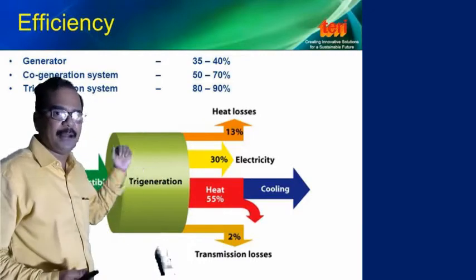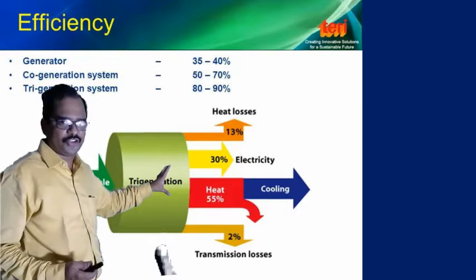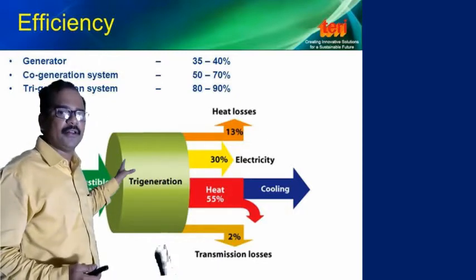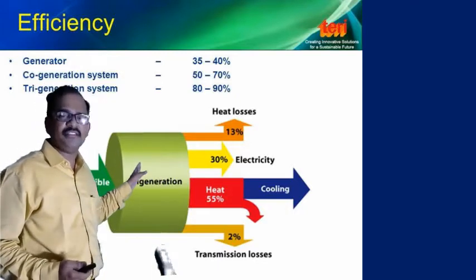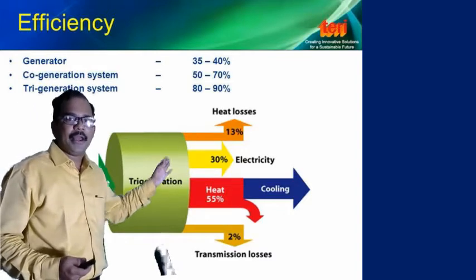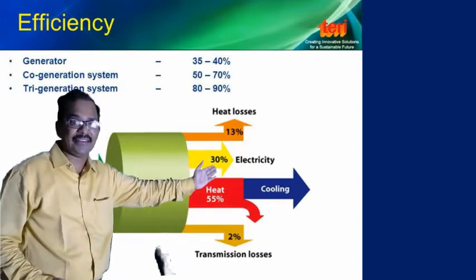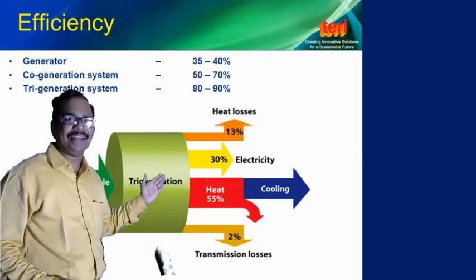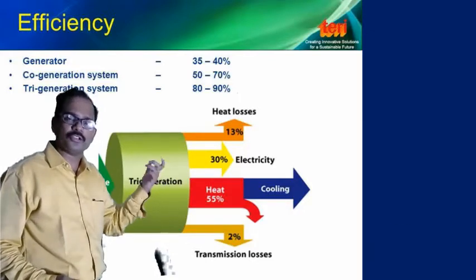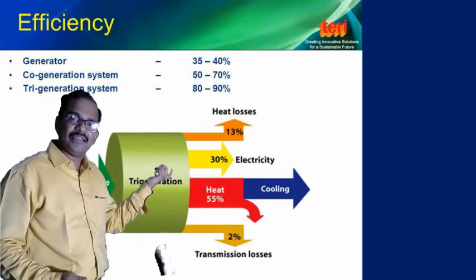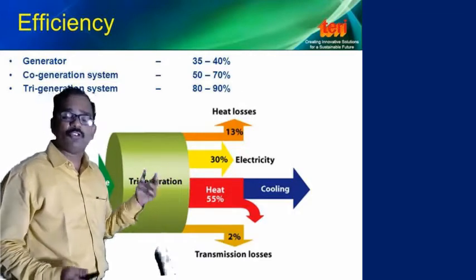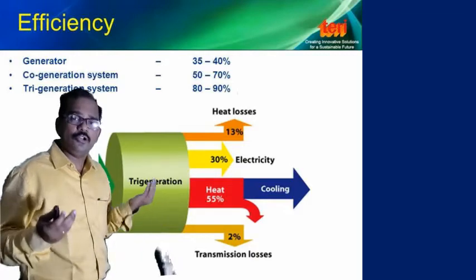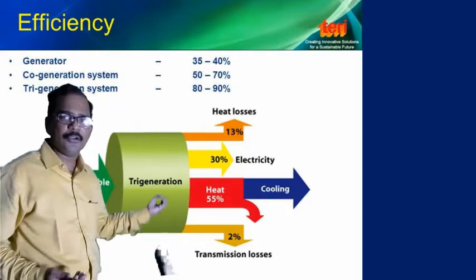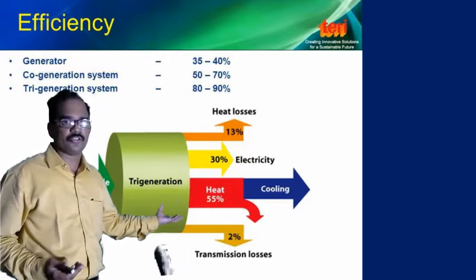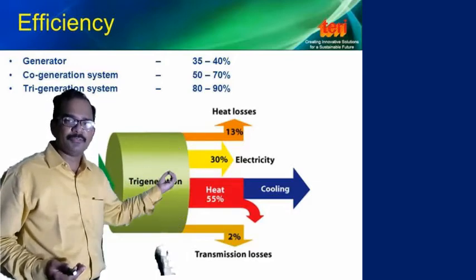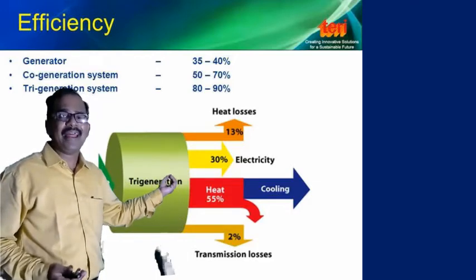You can see a typical example here. There is a trigeneration system. I have given 100% combustible fuel. That is, a fuel is combusted, and then I am getting 30% electricity and 55% as heat and cooling. Both are called thermal energy. It may be either heat or cooling. And what is the leftover 15%? That is losses. 13% heat losses and 2% transmission losses. So overall 30% electricity plus 55% heat and cooling.